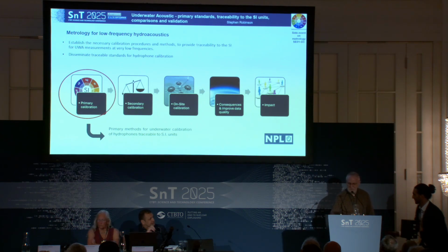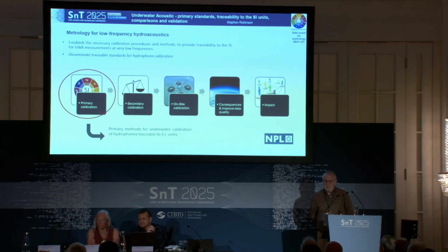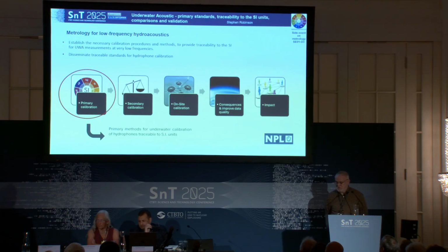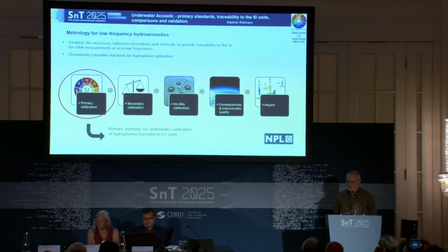Does that work? Okay, right. This shows essentially the same message again: we're talking about the primary calibration, but ultimately there's usually a secondary calibration method to calibrate the actual instrument, in this case the sensor, the hydrophone that's used in the field. You would also want some kind of on-site calibration method which can check those calibrations in the field, because once the devices are deployed they may change their sensitivity.